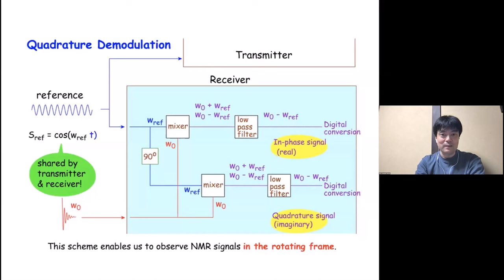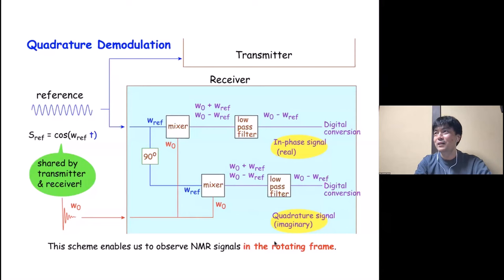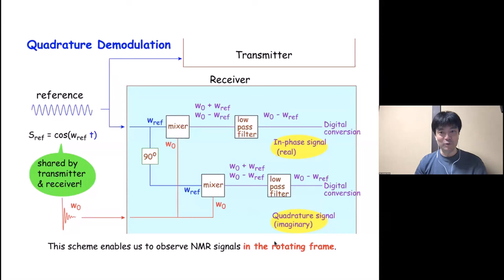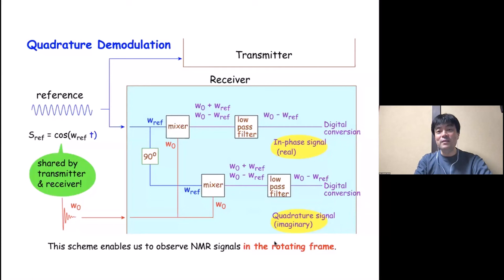That's it for the transmitter — let's now switch to the receiver. The function of the receiver is to convert the NMR signal, usually in the laboratory frame, into the rotating frame. From a theoretical viewpoint, it's quite usual in NMR to think about spin dynamics in the rotating frame of reference, since we ourselves are living in the laboratory frame and don't rotate at hundreds of megahertz.